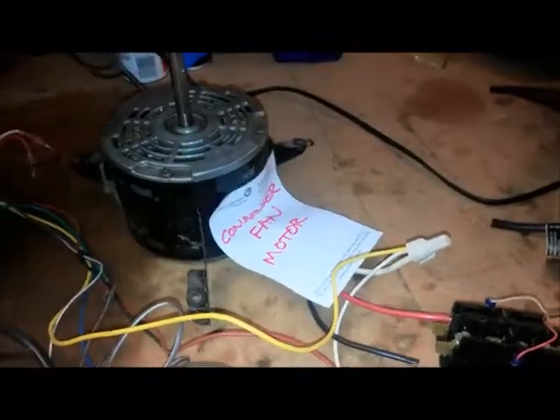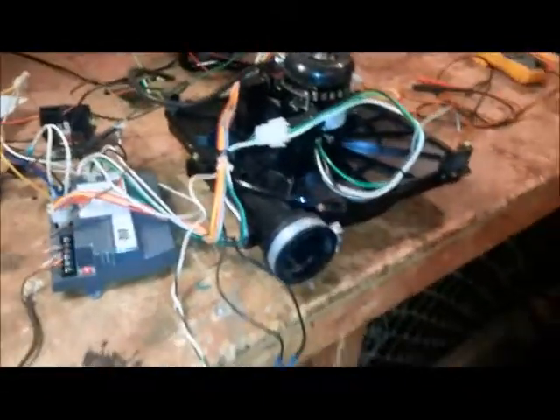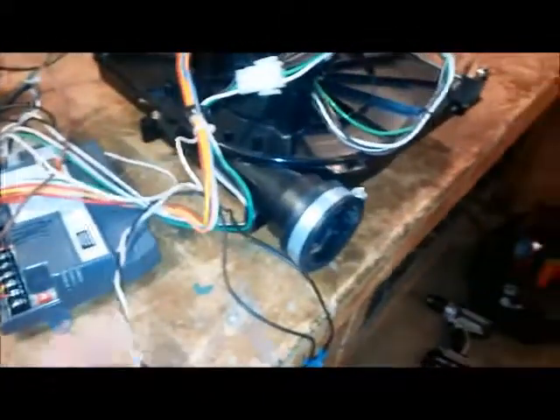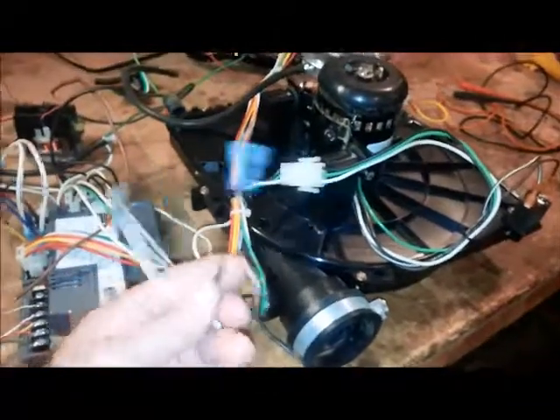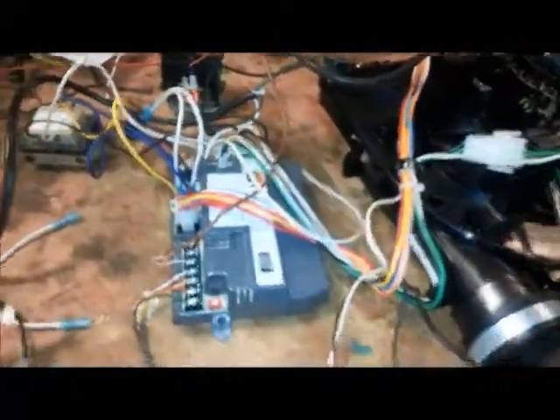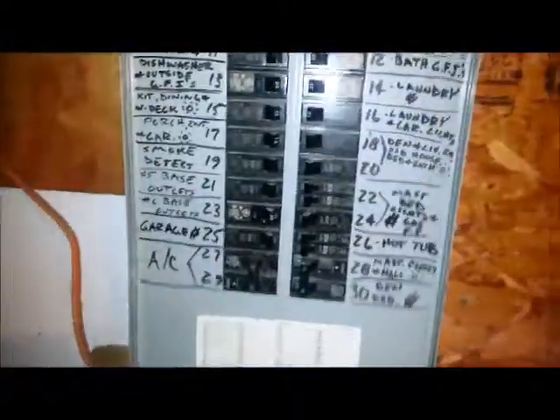Contactor, condenser fan motor. All right, so to start off with, we need power, obviously. So your power is typically connected to the board from the main breaker box in the house by these two wires. Today we're using just a cord that's going to plug into the wall, tied into the board, common and line voltage. And if you don't know what your breaker box looks like, that's what she looks like. It's probably in your garage or your basement. And hopefully you've got one that's labeled furnace somewhere in there, like I do.